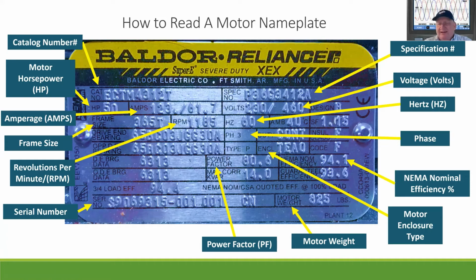So the other factors you're going to gain is you're going to have more heating in the bearings and those things that are not necessarily already necessary. So you really want to pick out, the idea would be, a Class H insulation. That means the company has really spent the money on putting a high efficiency or high class temperature device in it, but with a low temperature rise. And so the motor could actually run all the way up to 50 degrees centigrade, which then allows you to be at 110, 120 degrees, and the motor doesn't have any problem at all. You also want to look at that centigrade rating on the VFDs themselves, so those get properly set.